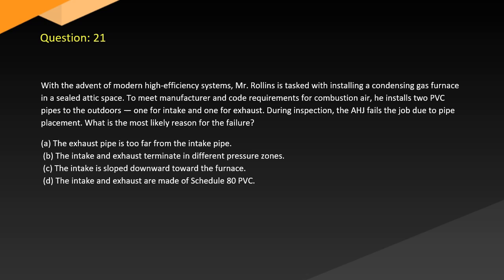Question 21. At the advent of modern high-efficiency systems, Mr. Rollins is tasked with installing a condensing gas furnace in a sealed attic space. To meet manufacturer and code requirements for combustion air, he installs two PVC pipes to the outdoors, one for intake and one for exhaust. During inspection, the AHJ fails the job due to pipe placement. What is the most likely reason for the failure? A. The exhaust pipe is too far from the intake pipe. B. The intake and exhaust terminate in different pressure zones. C. The intake is sloped downward toward the furnace. D. The intake and exhaust are made of Schedule 40.